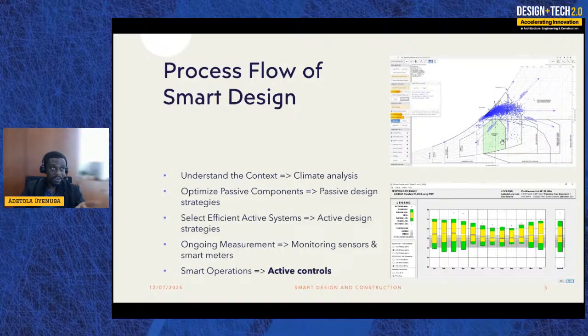And this shows that only less than 5% of the year is comfortable in this space. The design strategies required to move all the blue dots down towards the green zone will be dehumidification and cooling. So analysis like this, taken over the year, would enhance the ability of designers to fine tune their design. Because if it's a school, for instance, schools are shut down during summer holidays, you can see the patterns, like the temperature range below. You can design your HVAC system in such a way that when it is not required, the whole system is shut down. Because of that, you might find out that your peak load, which is normally what is designed for, will be lower because you're concentrating on when it is required and what your environment calls for.